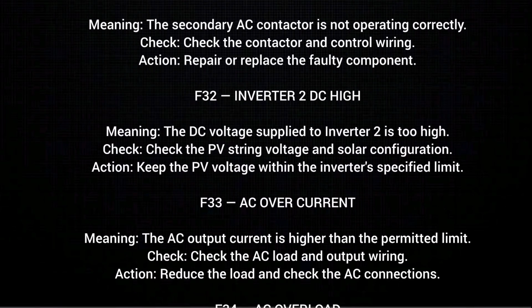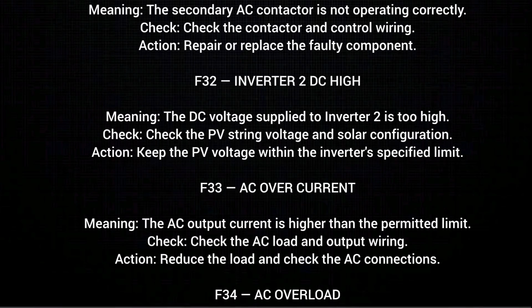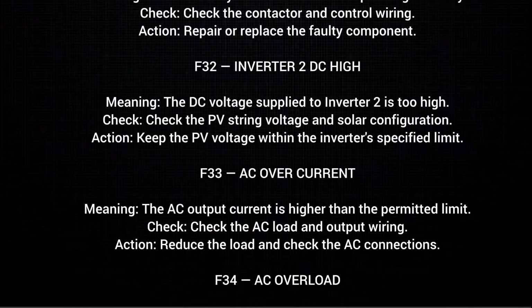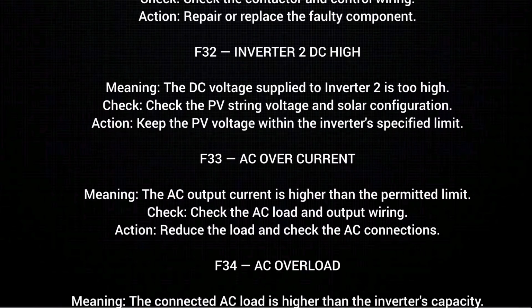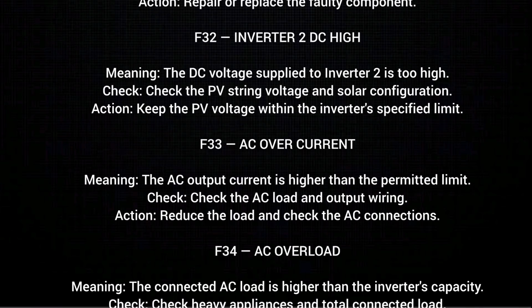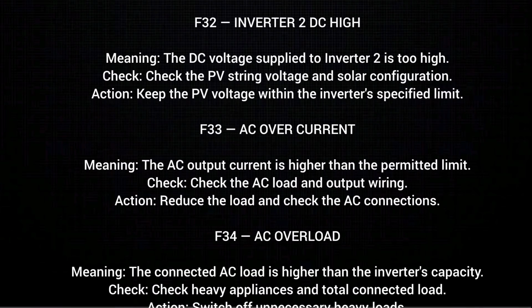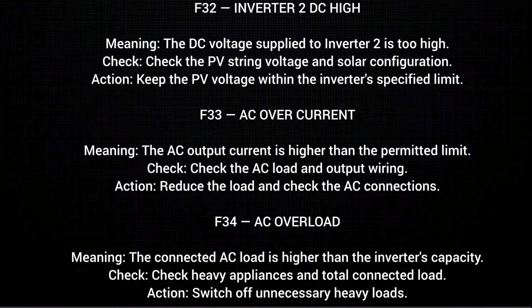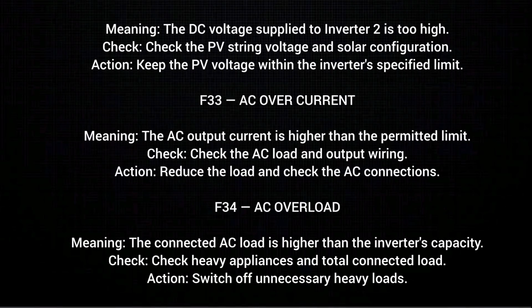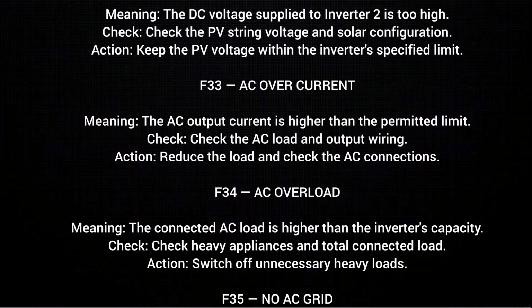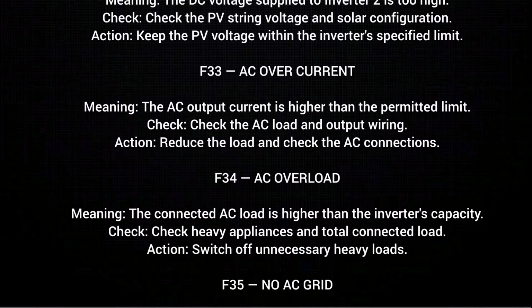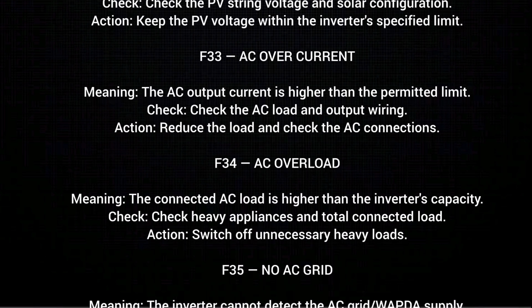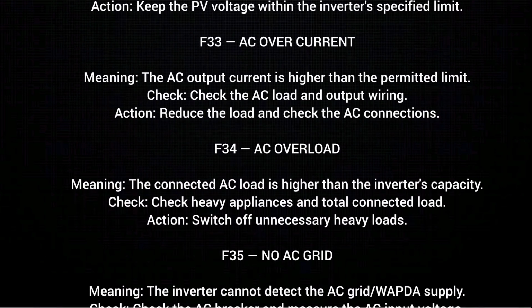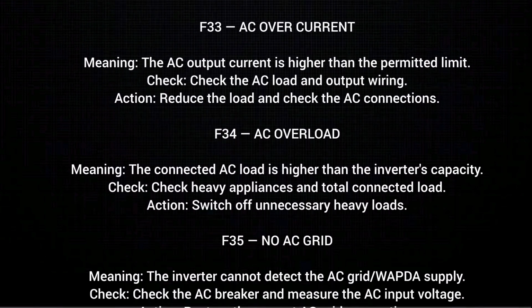F32. Inverter 2 DC high, meaning the DC voltage supplied to inverter 2 is too high. Check. Check the PV string voltage and solar configuration. Action. Keep the PV voltage within the inverter's specified limit. F33. AC overcurrent, meaning the AC output current is higher than the permitted limit. Check. Check the AC load and output wiring. Action. Reduce the load and check AC connections.